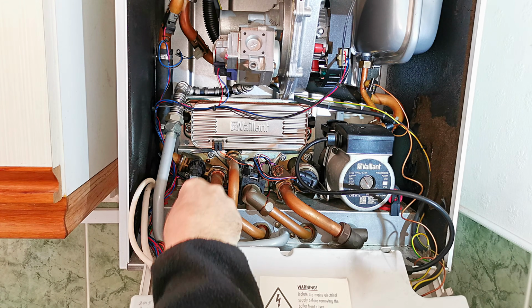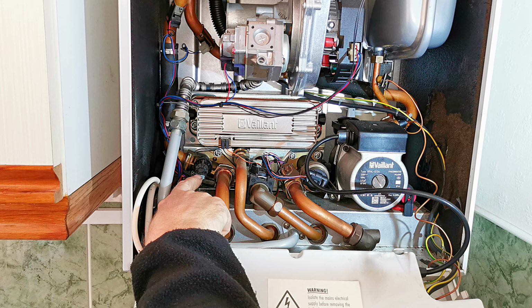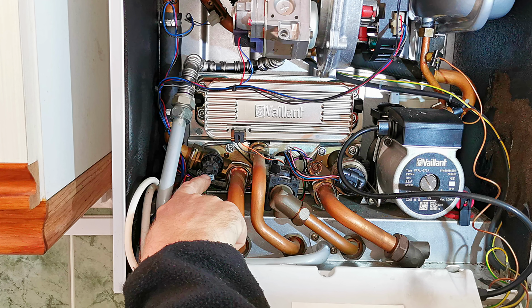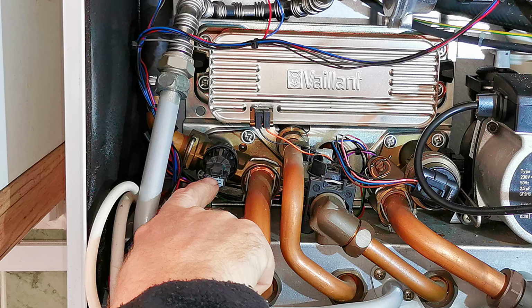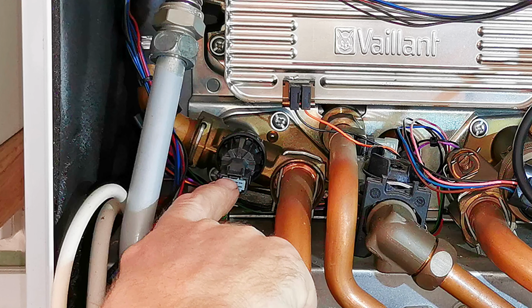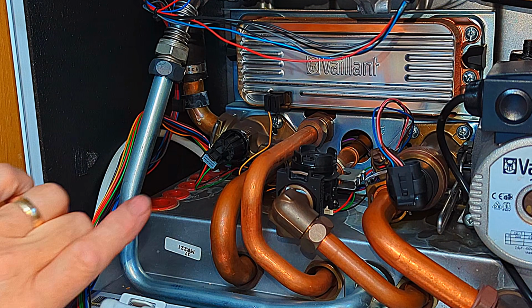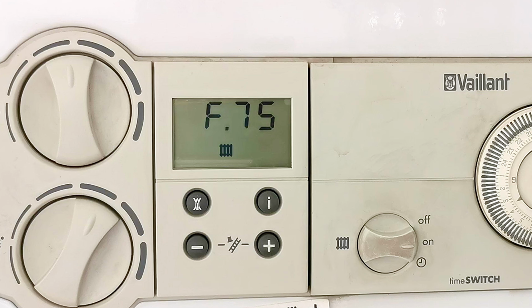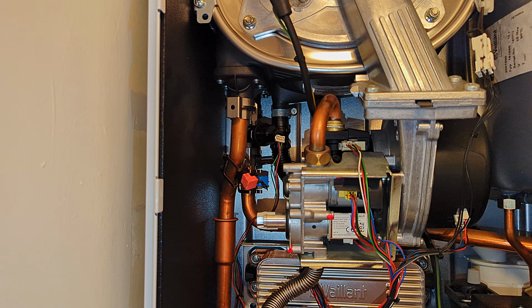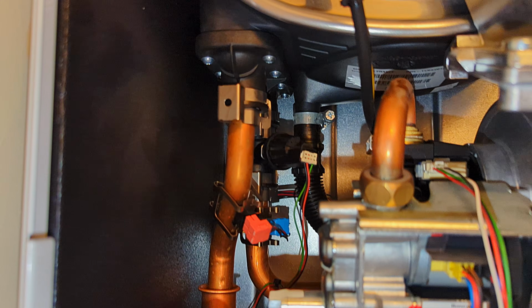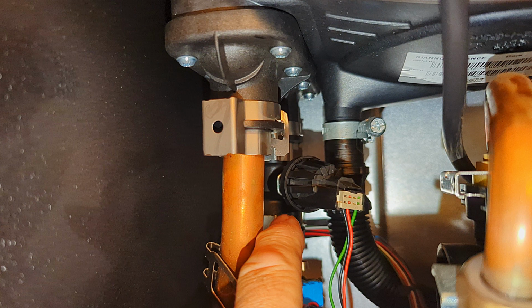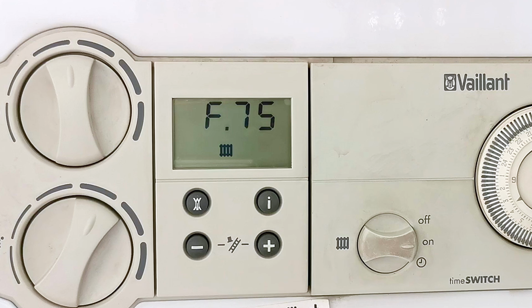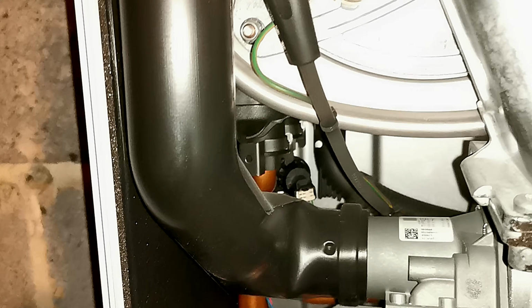Here's a bit of technical information for you about the pressure sensor position. On the earlier Ecotec boilers, the pressure sensor was down at the bottom here, and that is after the main heat exchanger. As we know, over time we may get some resistance through the main heat exchanger, which will lead to some pressure loss. And if the pressure sensor is getting a little sticky, that could lead to the F75 fault. On the newer Vaillant boilers, they moved the pressure sensor so it was on the pipework directly after the pump, so before the main heat exchanger. That removed a lot of problems with boilers coming up with F75 because the pressure sensor was after the main heat exchanger. Also, having the pressure sensor before the main heat exchanger means it runs a lot cooler, which is obviously much better for the pressure sensor.